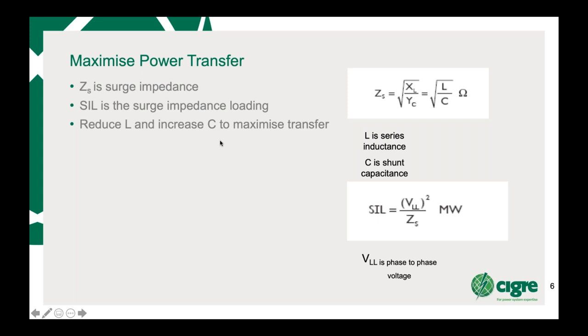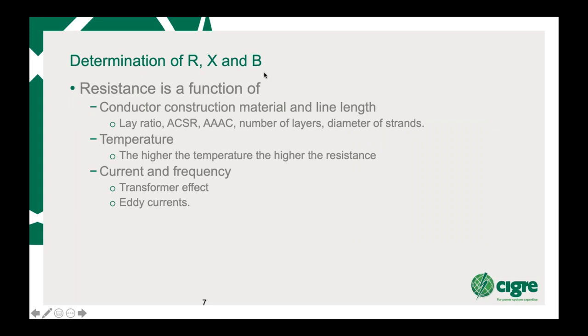Determining R, X and B, which will then link to L, C and R, we need to look at what makes up the resistance of a particular conductor. And really, the resistance is dependent on the construction of the conductor, material, and line length, of course. The conductor resistances are dependent on the lay ratio, that's how tightly the conductor is wound, and then, of course, whether it's an ACSR, a triple AC, or any other kind of conductor. Then we're also looking at the number of layers, diameter of strands, and so on, which will affect the resistance. Also, the temperature of the conductor: the higher the temperature, the higher the resistance.